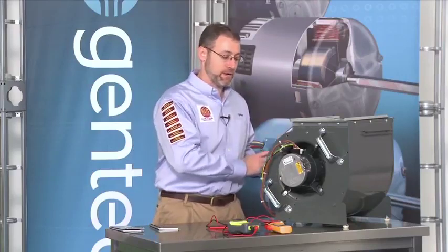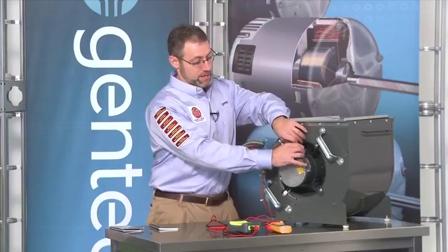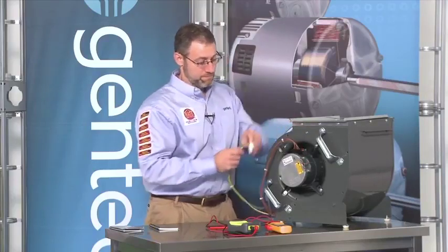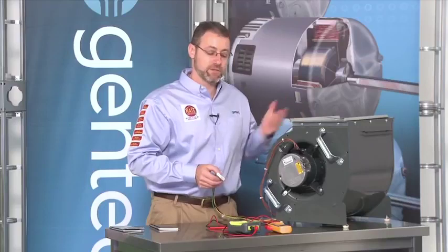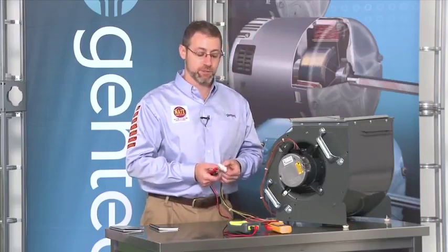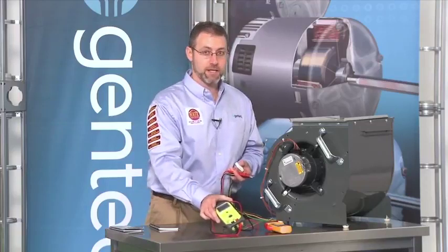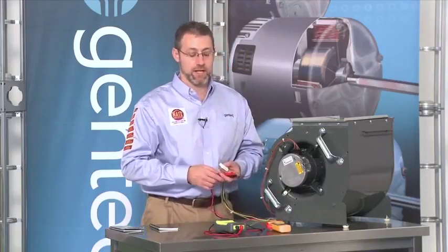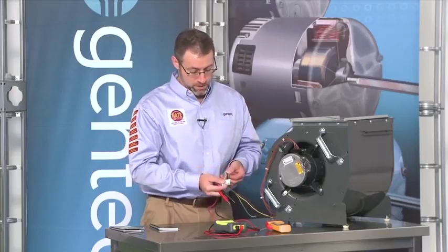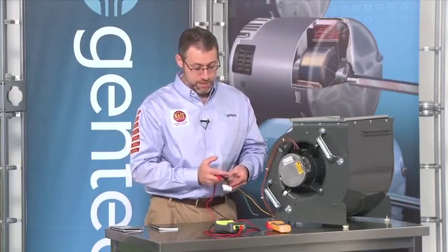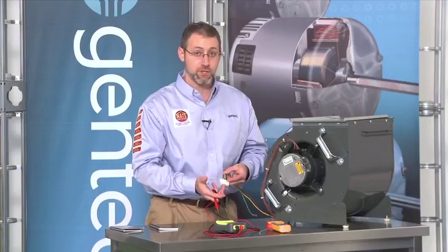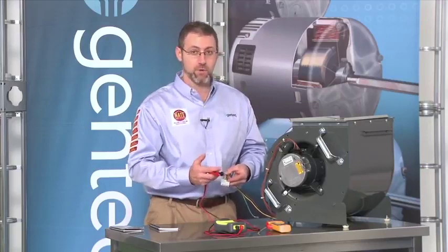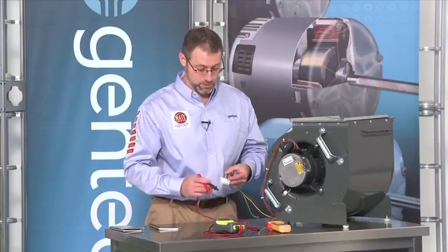So I would turn the power off, disconnect my high voltage plug, turn the power on my system back on, and then check the voltage on my high voltage plug. And we can use just about any voltage meter to make this check. You can even use a standard analog meter. So on this plug, we would then identify by wire colors, by wire position, and from our manufacturer's schematic what is L1, what is ground, and what is neutral.